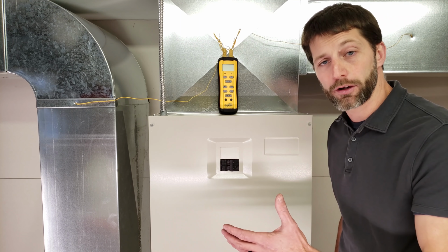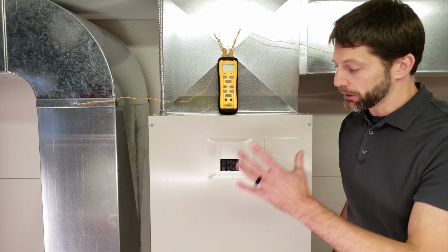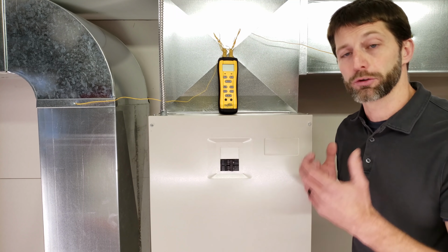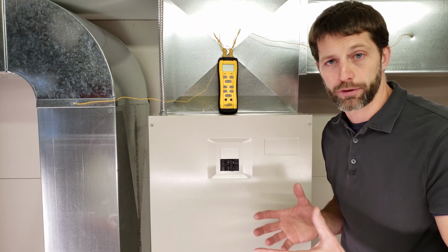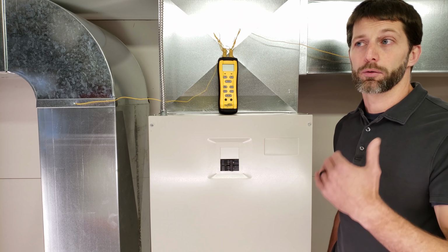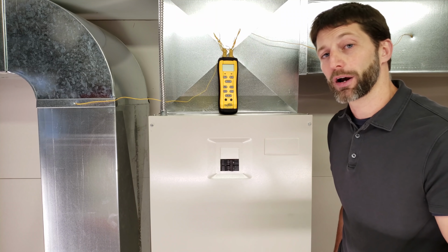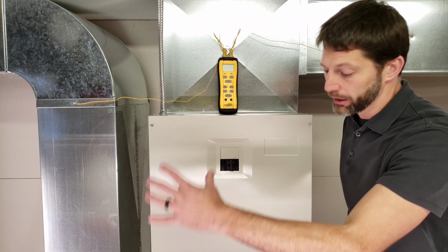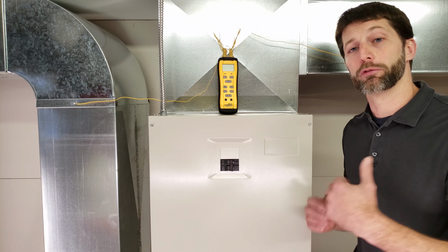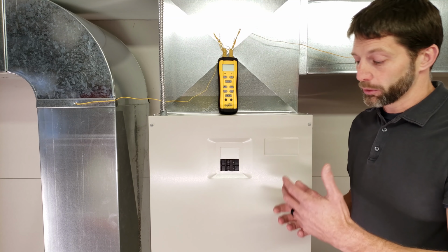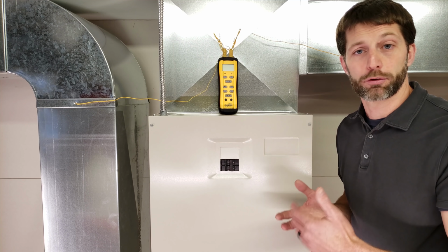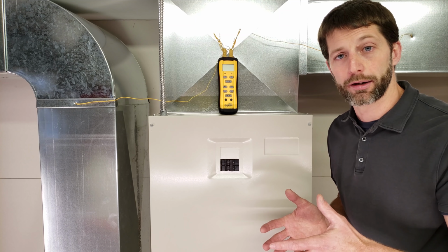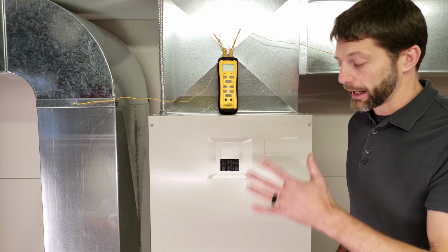If you measure higher than a 21 degree Delta T at your indoor unit and you have a single or two-speed outdoor unit, you could have low airflow. So that could be the issue. And what that means is basically you're not providing enough heat from inside the building, which is the heat in the air. You're not providing enough heat across the evaporator coil for the refrigerant to absorb. So because of that, you end up having a potentially higher Delta T. So you could have 23 degrees or 24 degrees. It's a telltale sign that you have low airflow at the indoor unit.